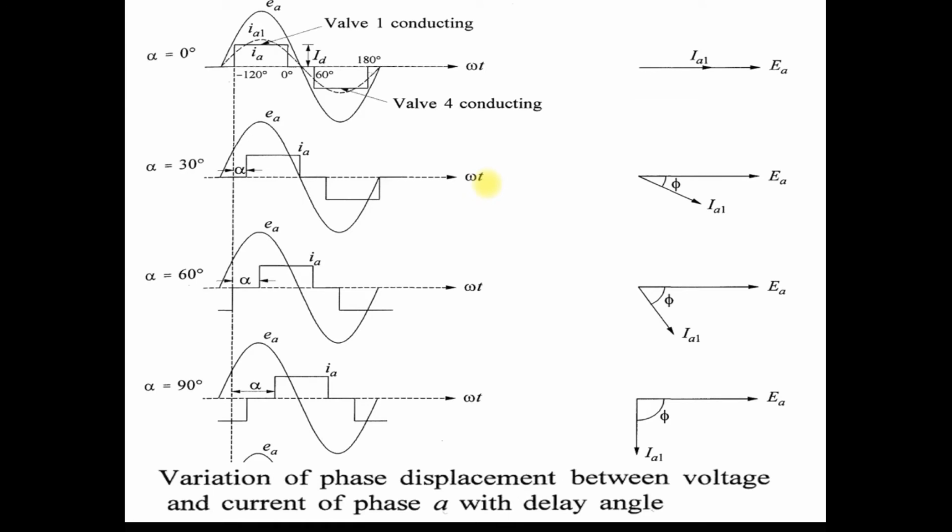and after that we understand the phase displacement between the phase voltages and line current. As you know, in the HVDC system, at the converter side, both the receiving side and sending side, we require a reactive power source. The reason for this requirement is that we cannot transmit reactive power from one end to another end through the HVDC system.